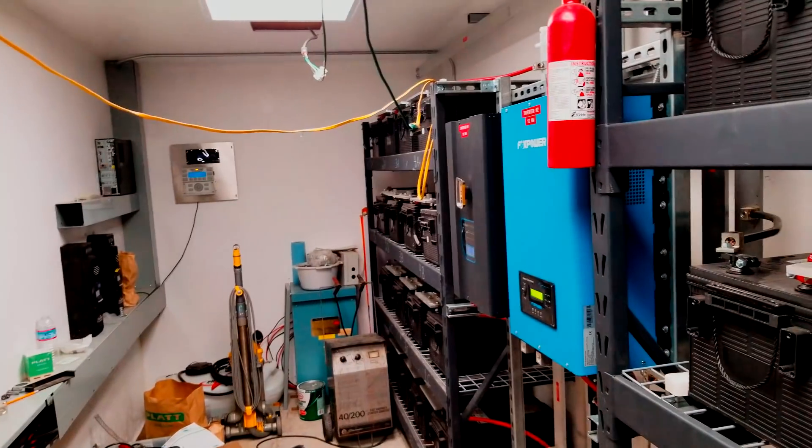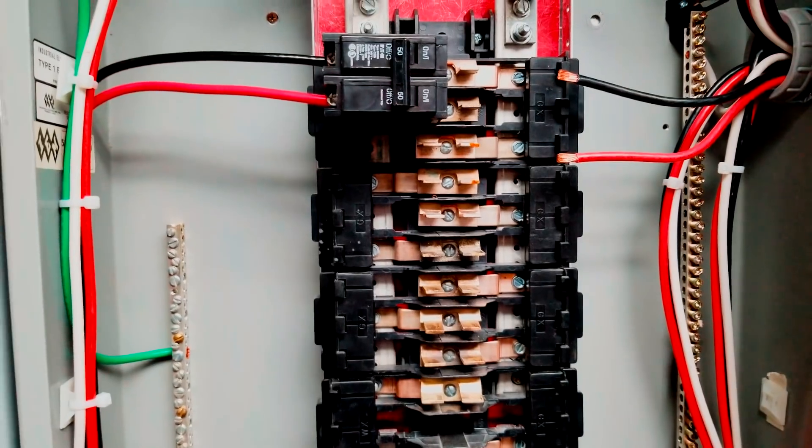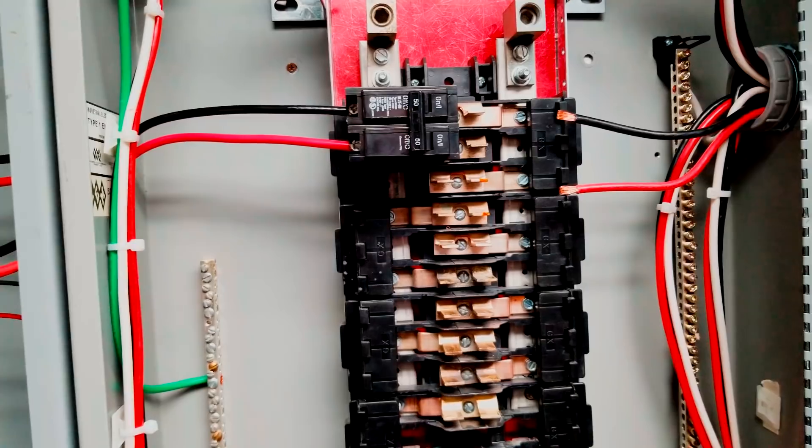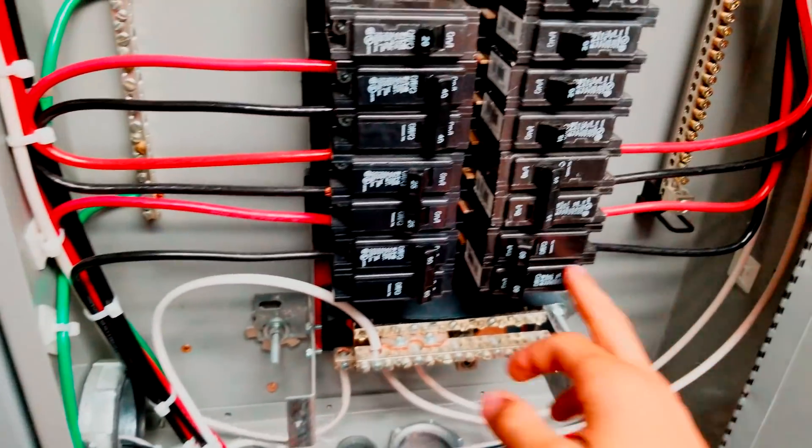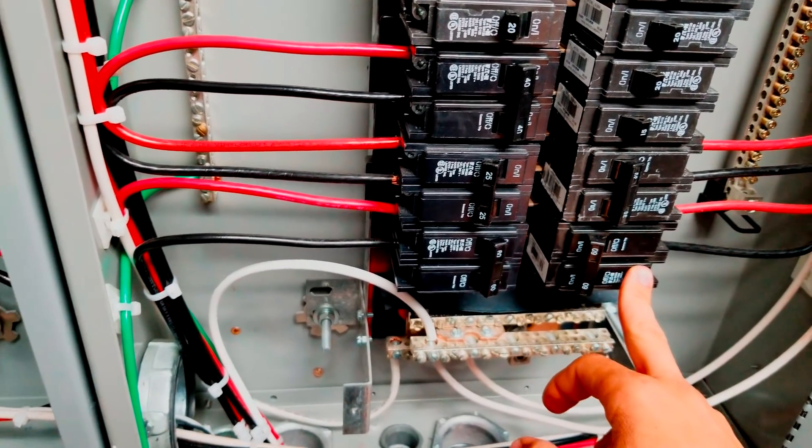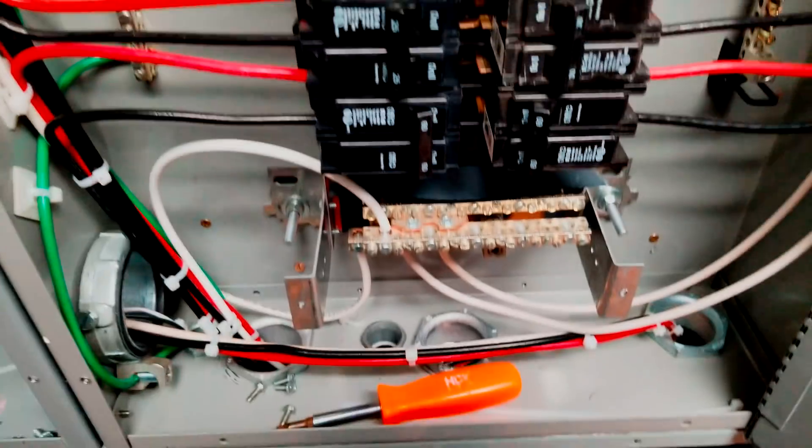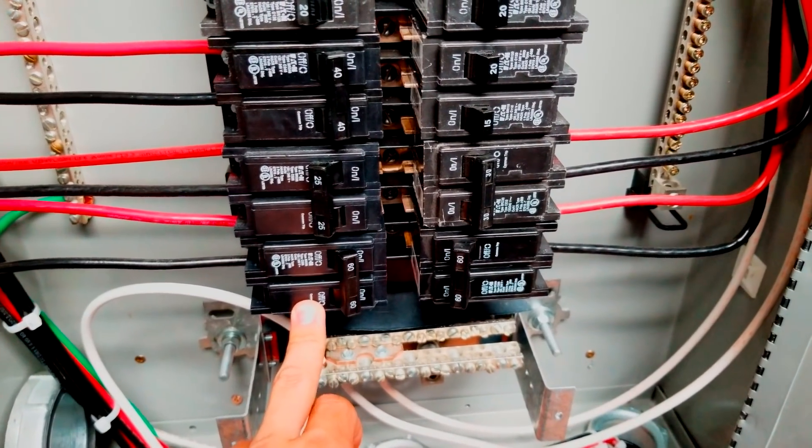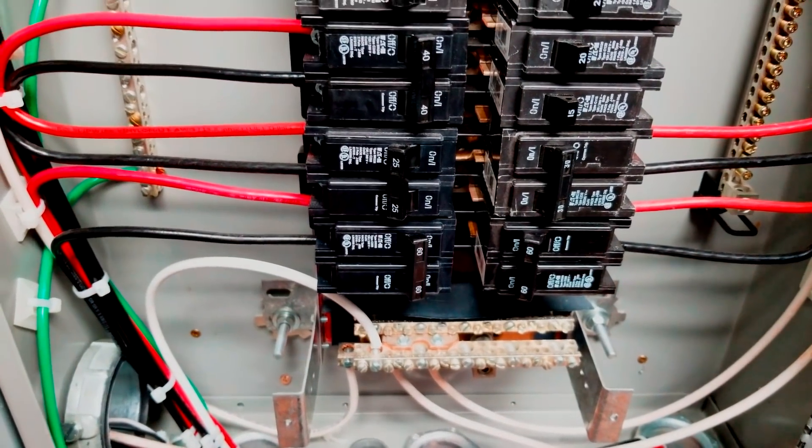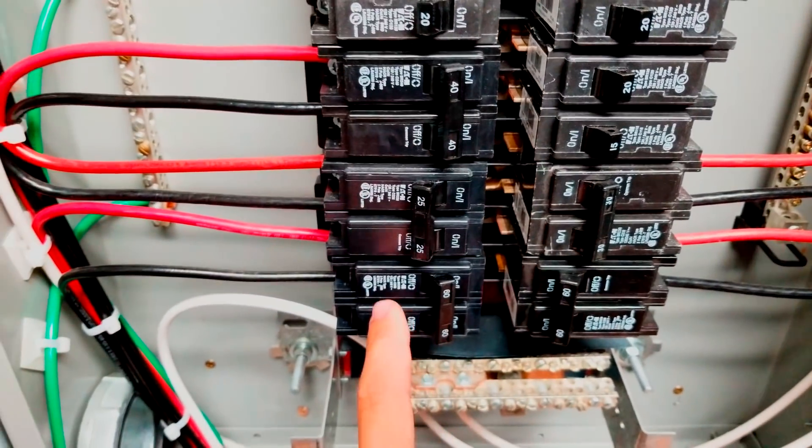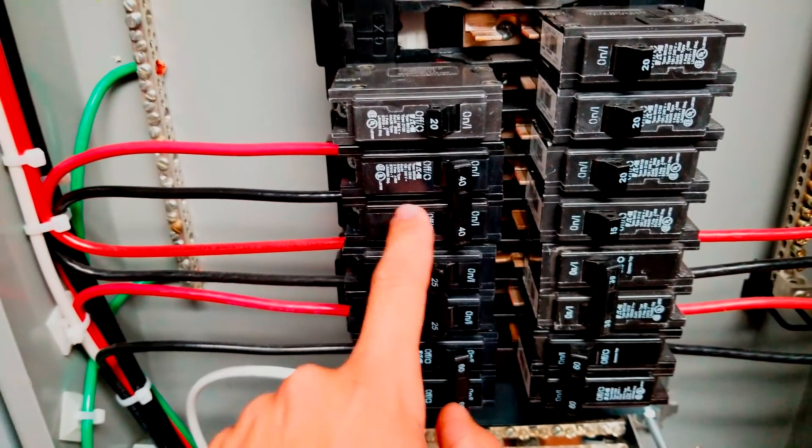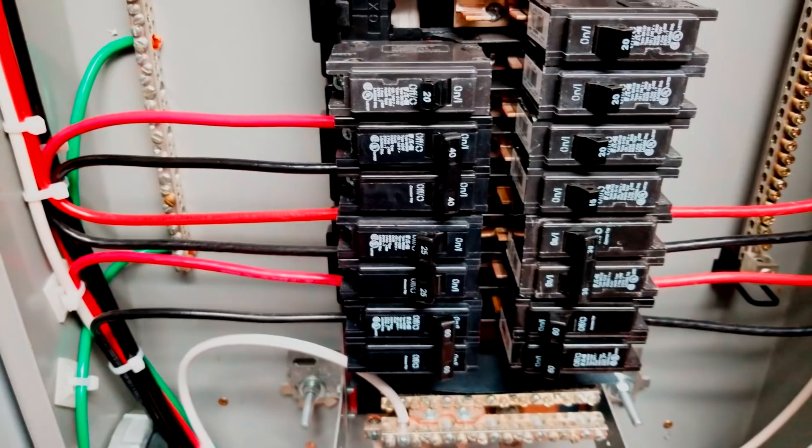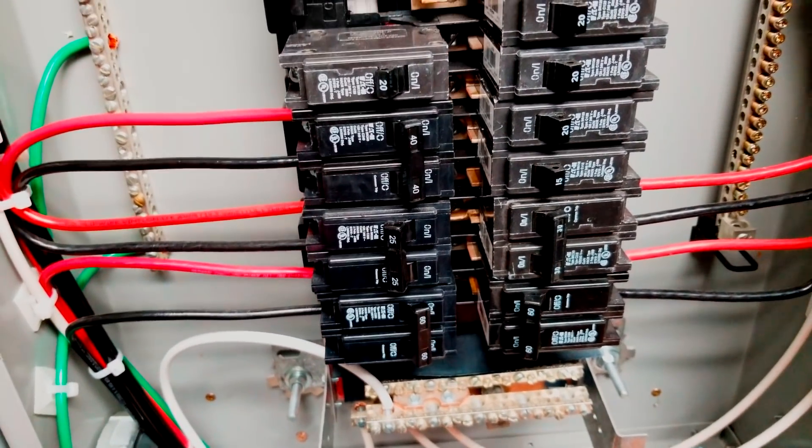And I have the blue inverter feeding this whole panel board. That's my main distribution. And then the black inverter on the left feeds this top section of this split bus panel. Currently I don't have anything running out of here on this top section because I'm using that inverter. I have my input from my generator, this 60 amp breaker. I have another 60 amp breaker that was going to the transfer switch—that's not really used, actually that's this 30 amp—and then I have a 60 amp breaker going to the blue inverter and a 40 amp breaker going to the black inverter.